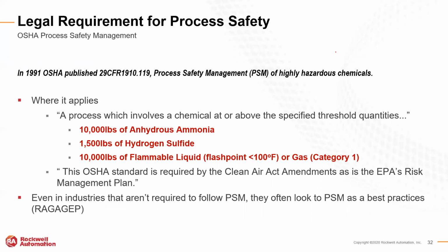That also has been made the law of the land via OSHA. So OSHA has a requirement called process safety management. And in 1991, they established 29 CFR 1910.119, and that is called Process Safety Management, or PSM. And they define some hazardous chemicals, hazardous gases that will be the thing that you're protecting against.